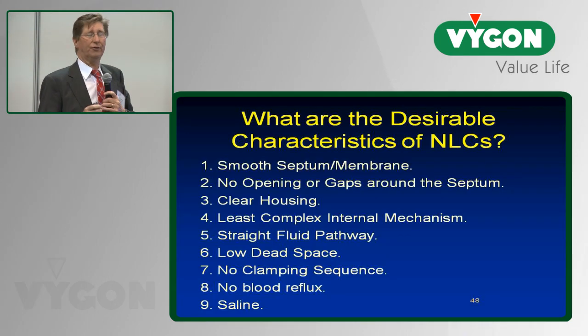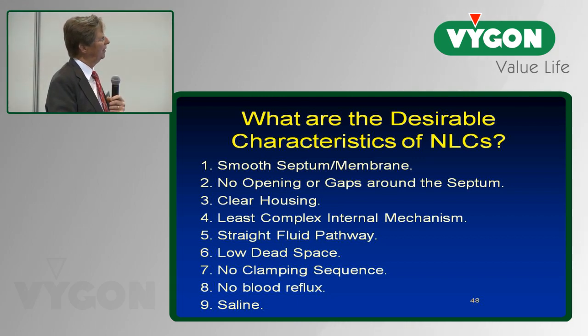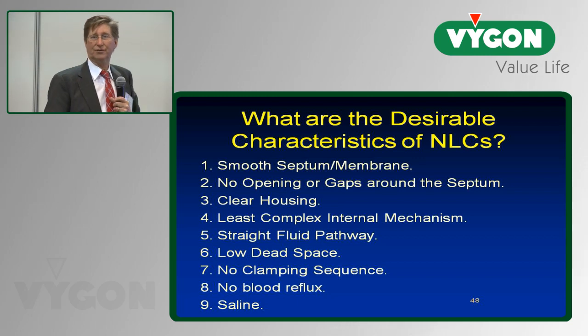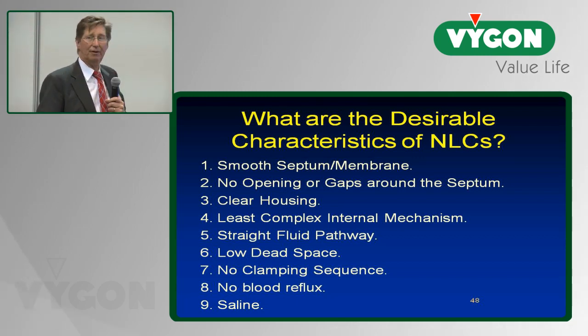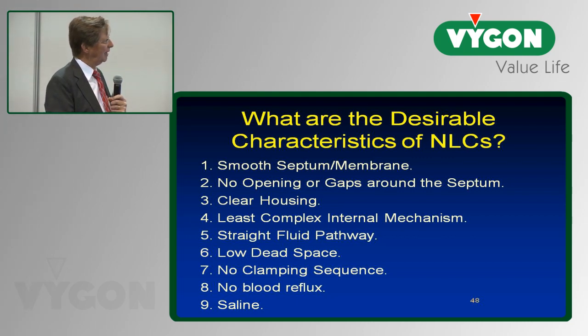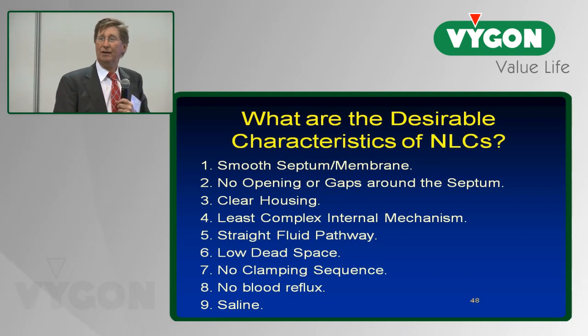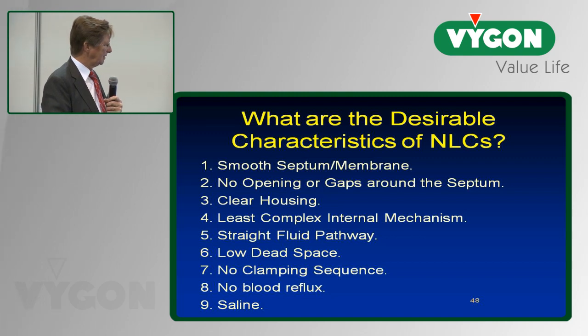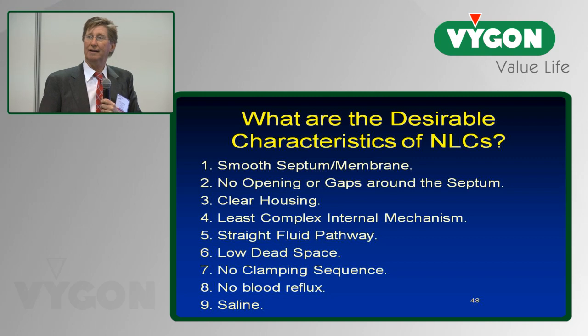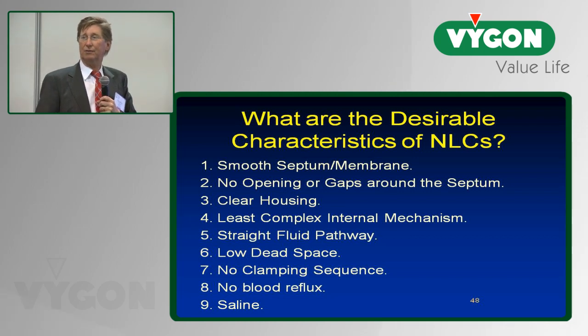If we look at desirable characteristics of needleless connectors: first, a flat, smooth, easy-to-disinfect external surface. Second, no opening or gap around the septum seal where the septum connects to the housing. Third, clear housing. Fourth, least complex internal mechanism. Fifth, a straight fluid path. Sixth, minimum dead space. Seventh, no requirement for a clamping sequence so that clinicians aren't confused. Next, no blood reflux. And last, being able to flush with saline, since heparin-induced thrombocytopenia (HIT) is an issue—so if we can avoid use of heparin by using saline, it would be beneficial.